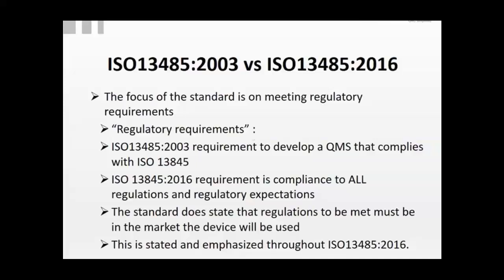Kind of ingenious. Instead of pointing out the differences between every regulation, which would have been a nightmare, they said, okay, you are in that industry. It's your responsibility to find out what those regulations are according to the market or where you manufacture, depending on how the regulation is set up. So in some countries, if you manufacture there, you have to meet the regulations. For example, if you sell in the United States and you make it in some other part of the world, you have to meet 820 there as well. It's saying that the standard now must be met across the whole device. That's a huge change also.